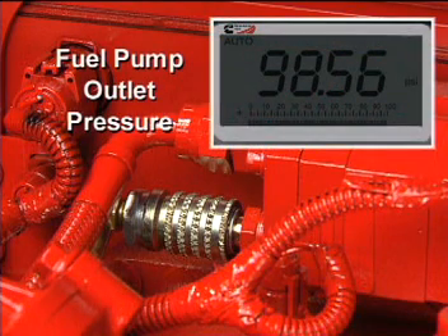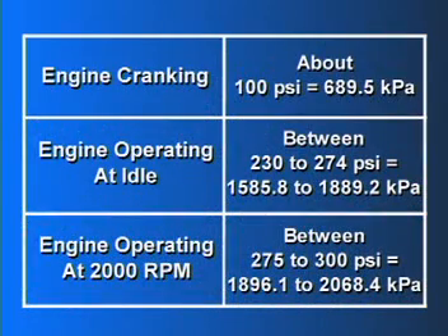Watch the pressure gauge installed in this fitting during engine cranking. The pump output pressure with the engine cranking should be approximately 100 psi. With the engine operating at idle, the fuel pressure at this location in the housing should be between 230 and 274 psi. With the engine operating at 2,000 RPM, the fuel pressure at this location in the housing should be between 275 and 300 psi.